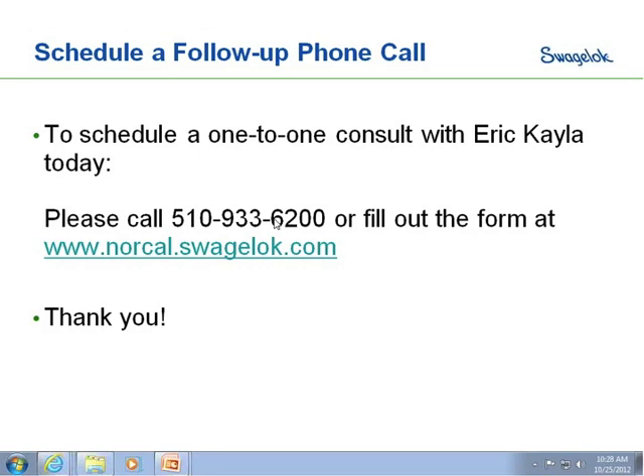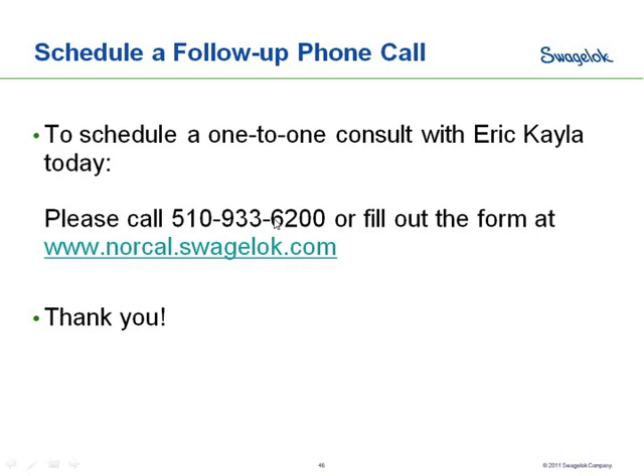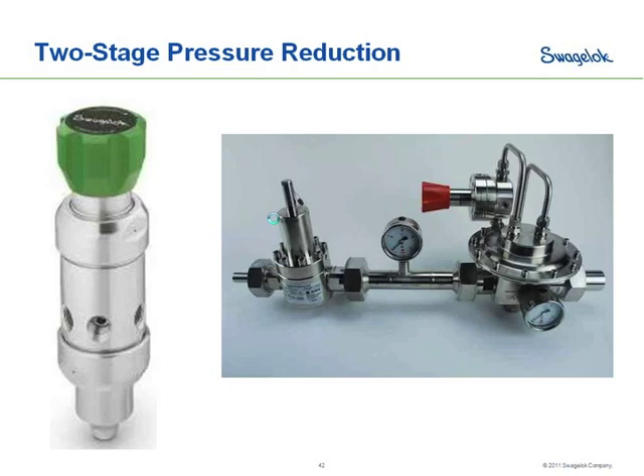One other quick question coming up. Can you describe the effect on supply pressure of the two-stage regulator? Okay, good question. So I'm going to back up here, if I can, to the two-stage regulator. If we look at the image on the right-hand side, it's a two-stage pressure regulator. We're going to have the supply pressure effect acting on both regulators. And we remember that it's an inverse effect. If we look at the picture on the right-hand side and assume flow is going from left to right, it's going to go first through that spring-loaded regulator and then second through that dome-loaded regulator.